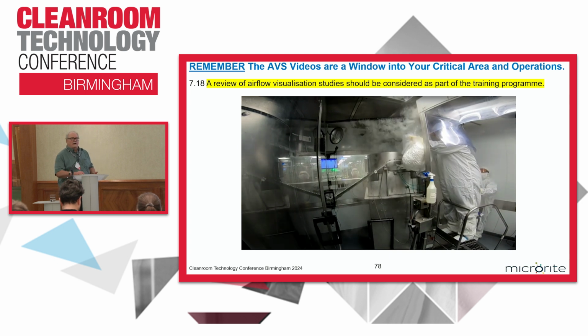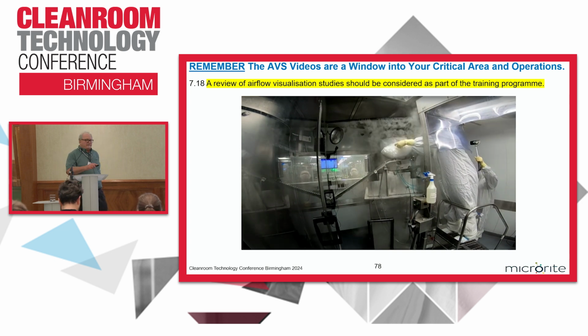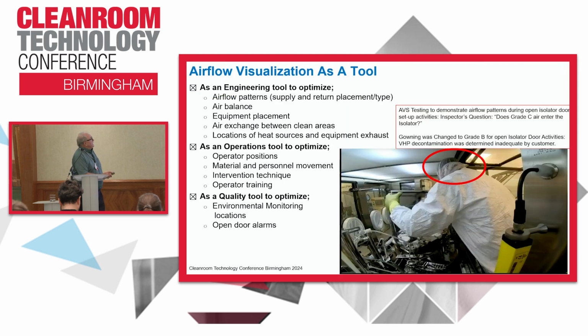All these things come in contact with the curtains, and this is one of the things that smoke studies help you understand what's actually going on, because you're looking at it. Airflow visualization is also a really good tool to help optimize airflow patterns, supply and return air placement, balance the clean room, placement of equipment, and it's a tool to optimize operator positions.